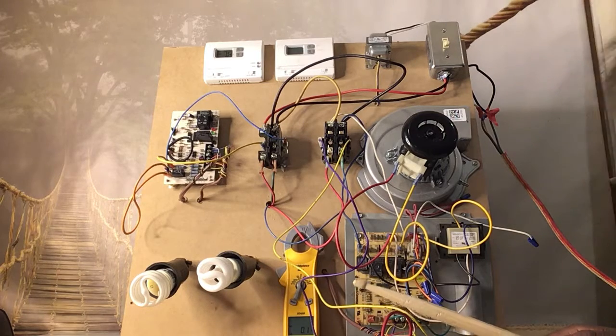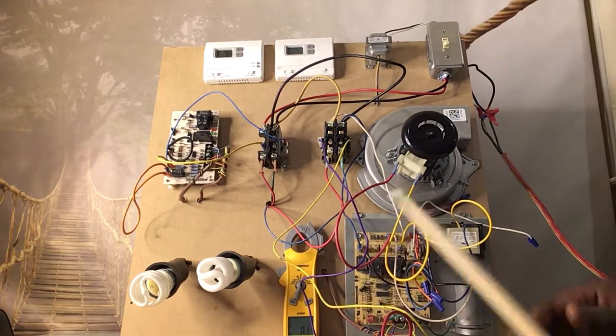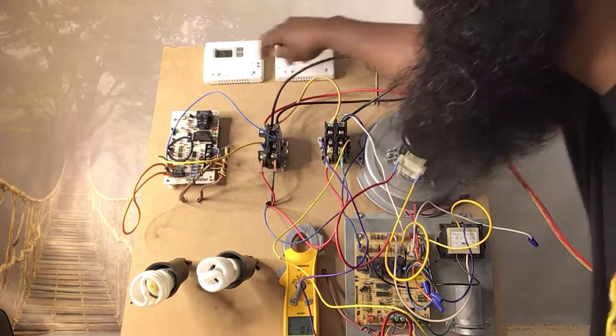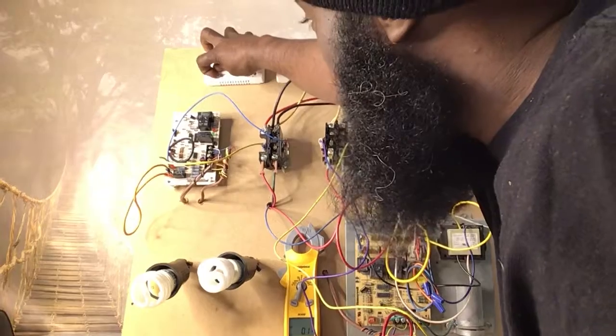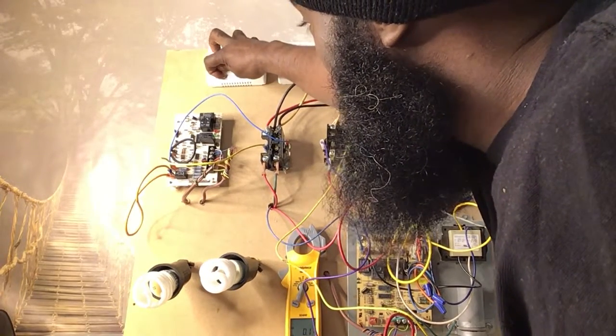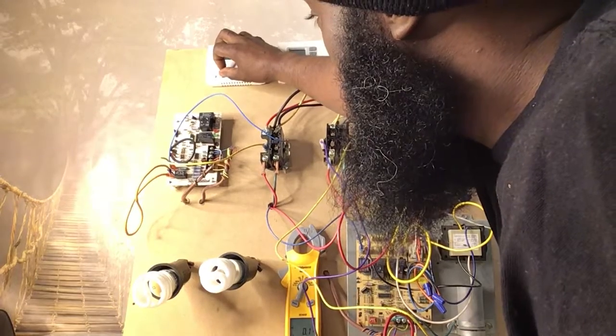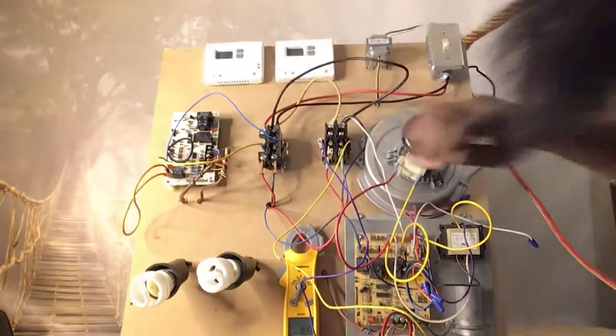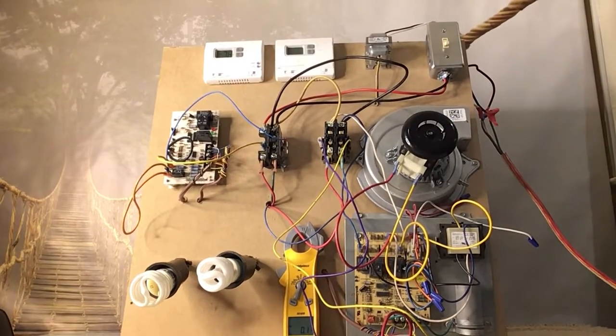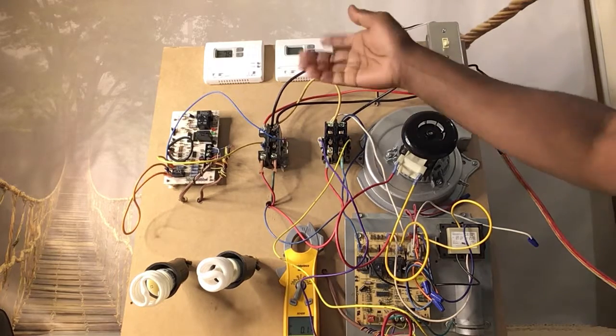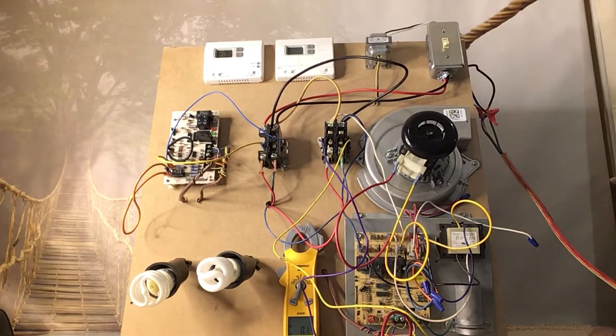All right, the first thing I am going to do is flip the switch on. Right now I have off on both of my stats. I want to make sure that they are all off. Emergency heat off. Okay. This one, the heat pump thermostat, looks like it has batteries in it. That's why it's on. I'm sorry, it looked like it has battery power because I know there's no power on it since we haven't flipped on the switch yet. This other stat that you see out is probably operating on 24 volts, which is why it is out. But in any event, let's flip on the switch and see what we got going on.